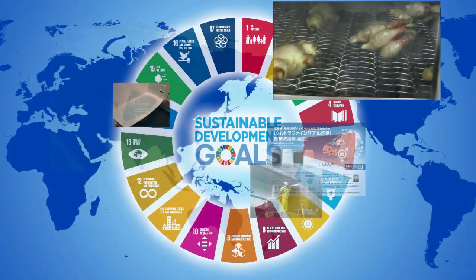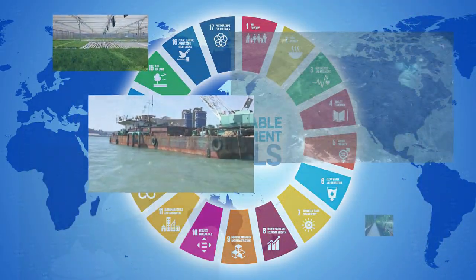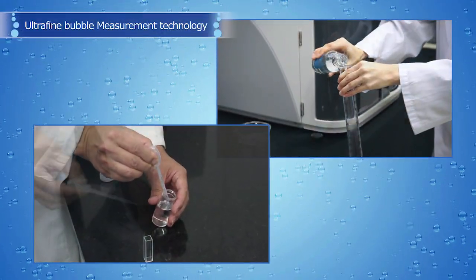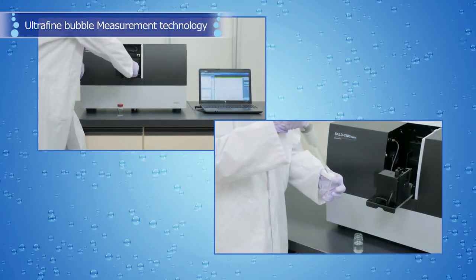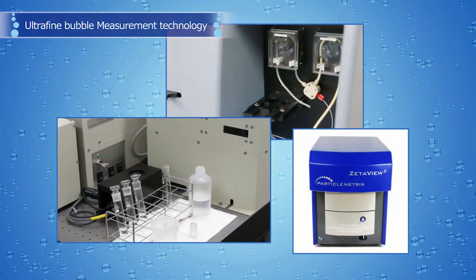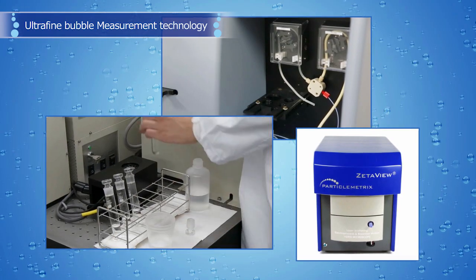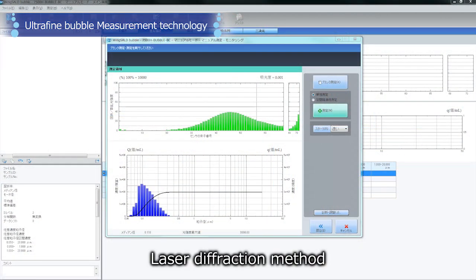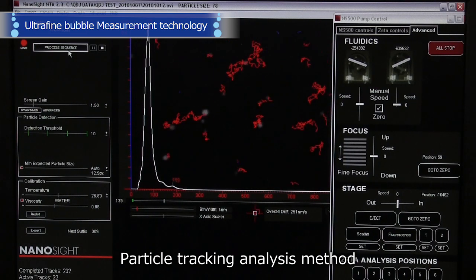These can contribute to the actions of sustainable development goals adopted by the United Nations. Ordinary optical microscopes do not work for the characterization of ultra-fine bubbles because their sizes are normally too small to see using the wavelength of visible light. Recently, various new techniques and instruments have been developed, including the laser diffraction method which measures angular intensity distribution patterns of scattered light from bubbles, and the particle tracking analysis method that analyzes Brownian motion speed in video images of bubbles.